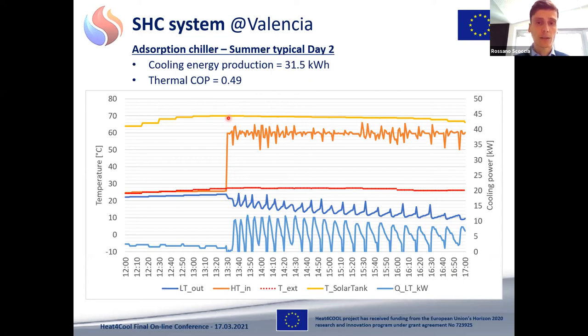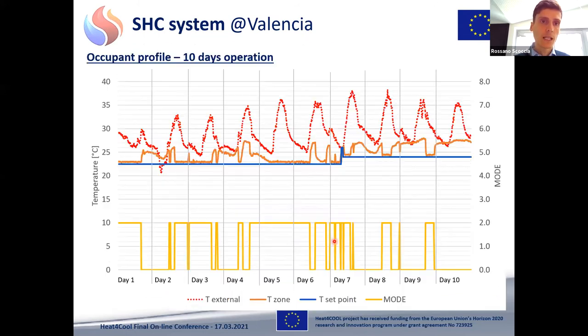Here you see that the solar collectors manage to heat up the water up to 70 degrees C, which is the threshold where the adsorption chiller turns on, and the adsorption chiller works from 1 p.m. to 5 p.m. with a constant inlet temperature of around 60 degrees C. The outside temperature is quite warm, around 30 degrees C. And you see that the cold water produced falls down to 10 degrees C. You also see the average cooling power of the machine, which is around 5 kilowatts.